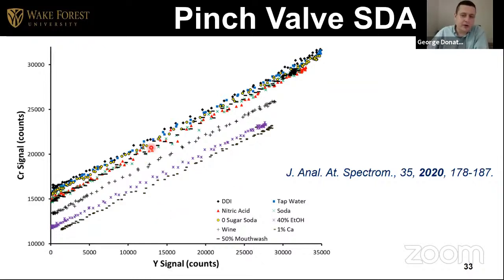For example, tap water here, I'm sorry, deionized water, up here, you have a certain intercept. And then when you have calcium 1%, which is one of the worst matrix effects, you have a much different intercept. That doesn't change the measurement because we use the second internal standard. Doesn't matter where it is. The only thing is, visually, you can see how bad that matrix effect is before you do the whole calculation.